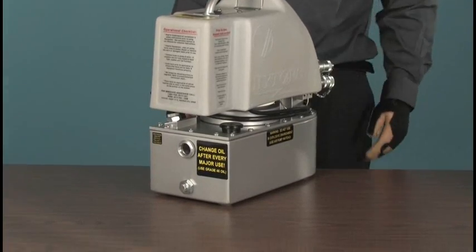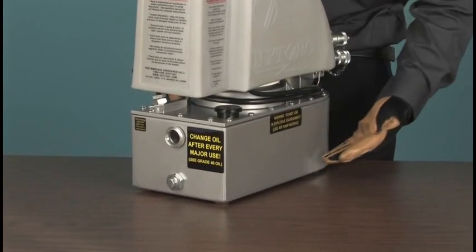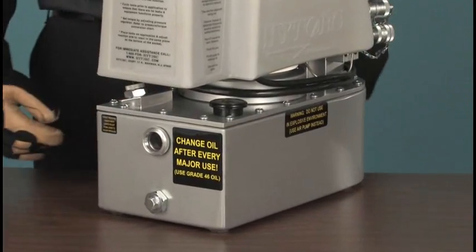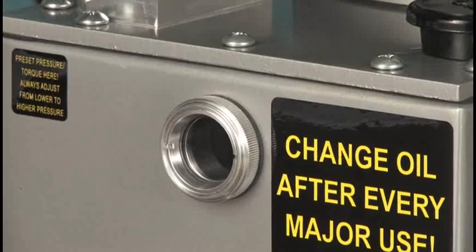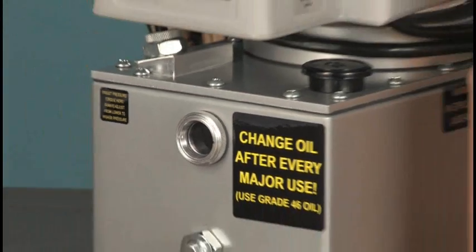The standard electric pump comes with a reservoir which should be filled to the fill mark or the middle of the sight glass indicator with ISO 46 hydraulic oil, which comes shipped with a new pump.